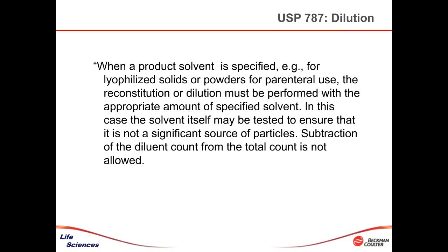Dilution. A lot of materials are thick, or maybe highly concentrated, or both. And in some cases, you cannot introduce it easily into a light obscuration system due to those factors. So maybe dilution is necessary. Under 787, they do discuss that, and they say that the effort to dilute needs to be carefully done. There's quite a bit of discussion of that in the informational chapter 1787, because by diluting a protein-based material, you may cause dissociation or potentially aggregation, just depending on the type of formula and various other aspects of the material. So dilution is allowed, but it must be carefully done.